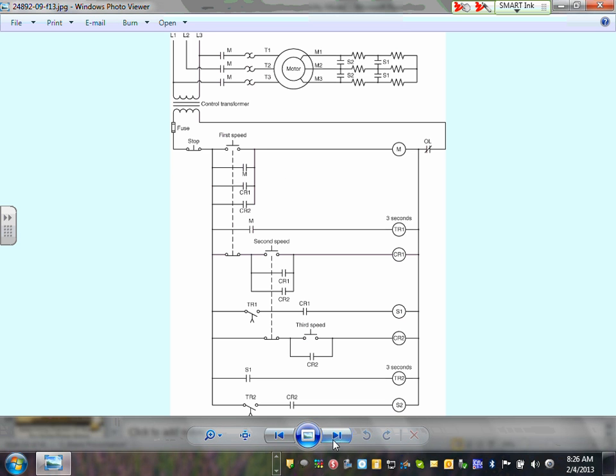So here's how it looks with the controller, my friends. When you start, the first speed, you connect. This is the first speed. This is second speed. Close these two. Third speed, which is the high speed, close these two. So they control the current in the rotor by closing contacts.